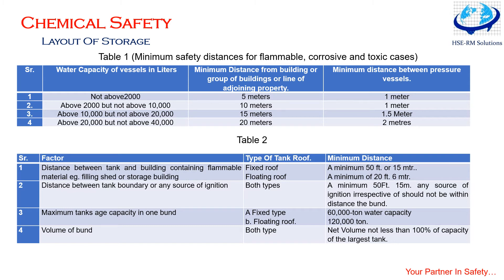For pressure storage vessels such as LPG, a full bund is not recommended because after spillage a large amount of liquid will remain after the initial flash-off. For example, approximately 67% of propane will remain in liquid form after the initial flash-off from a pressure storage tank of propane at 16°C. For fully refrigerated storage tanks containing liquid ammonia, a full bund should be provided.